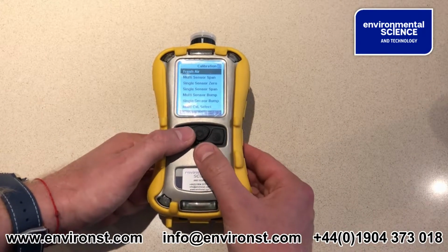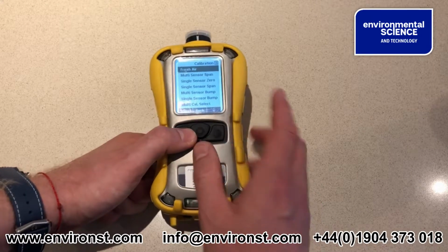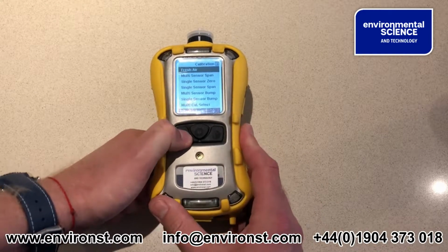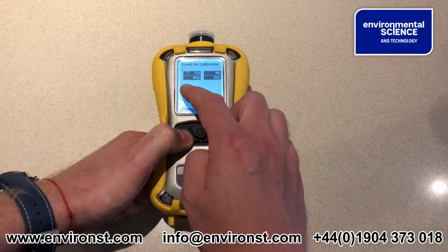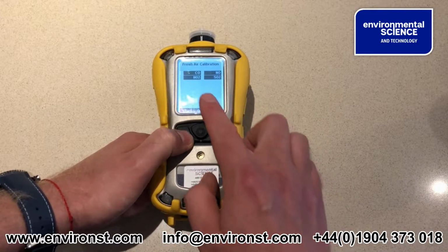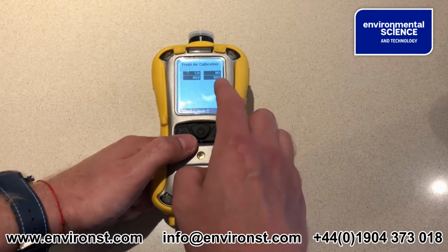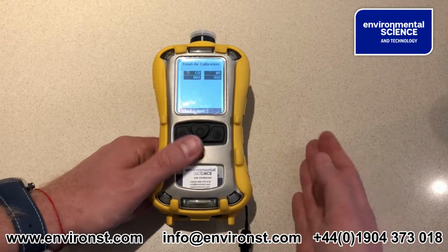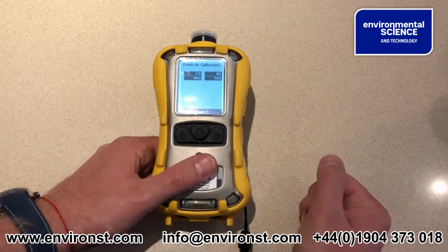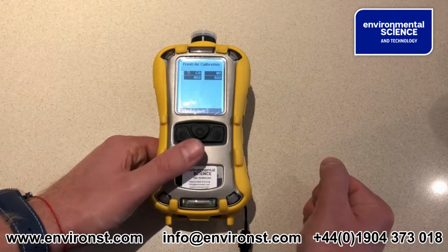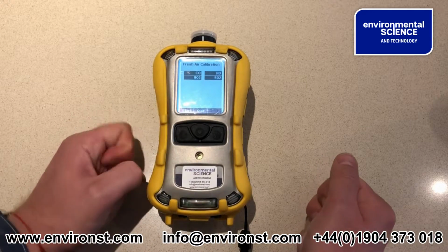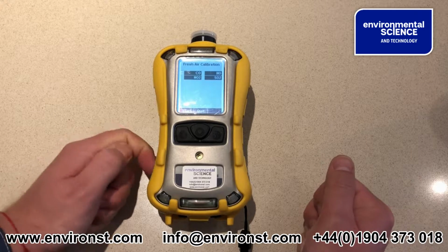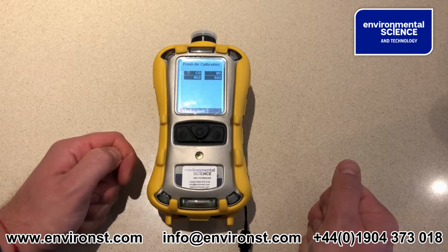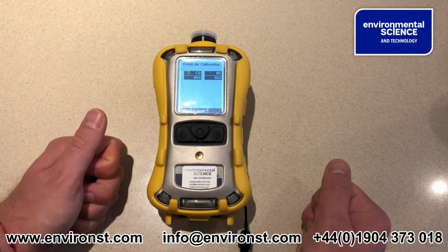So let's just do a quick fresh air calibration. If I press select here, that takes me to the fresh air calibration mode, and it's telling me that CO, NO2, NO and SO2 are calibratable using just fresh air. Things to make sure of in this situation are that we do actually have fresh air and that we've got none of these components knocking around, otherwise our zero point is going to be affected.